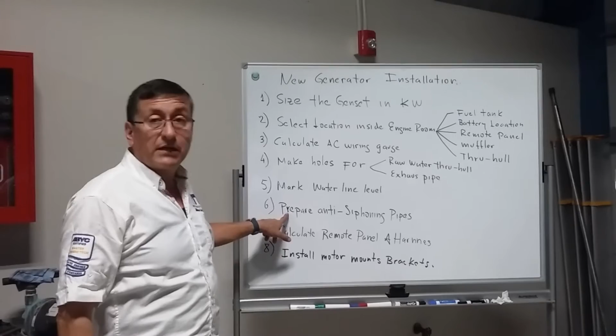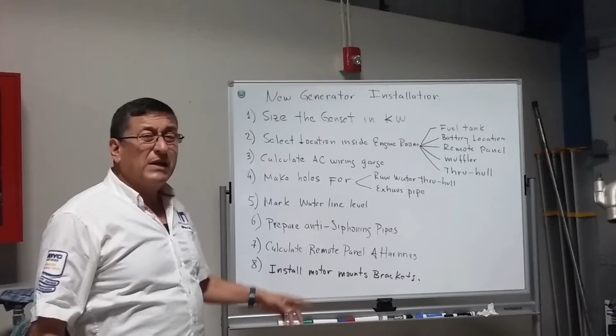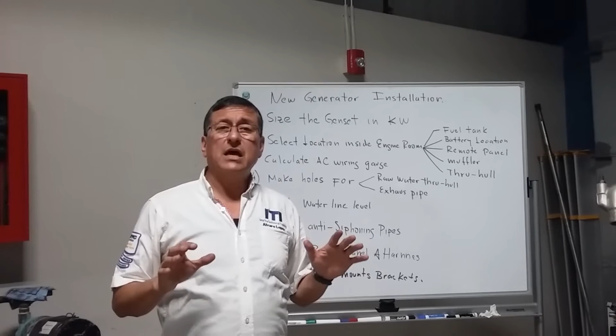And number 6 is prepare the anti-siphon pipes. And number 7 is calculate the distance in between the remote panel and the generator. And number 8, install the proper brackets and supports in order to support the generator properly. The generator produces excessive vibration, and the generator should be installed on proper supports, elastic supports, not rigid supports.